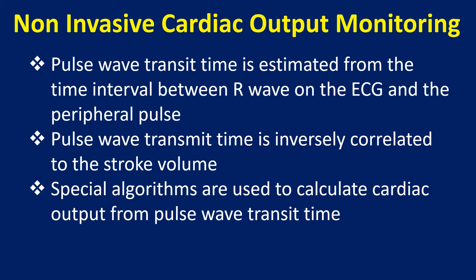Pulse wave transit time is estimated from the time interval between the R wave on the ECG and the peripheral pulse. Pulse wave transit time is inversely correlated to the stroke volume, and special algorithms are used to calculate cardiac output from it.